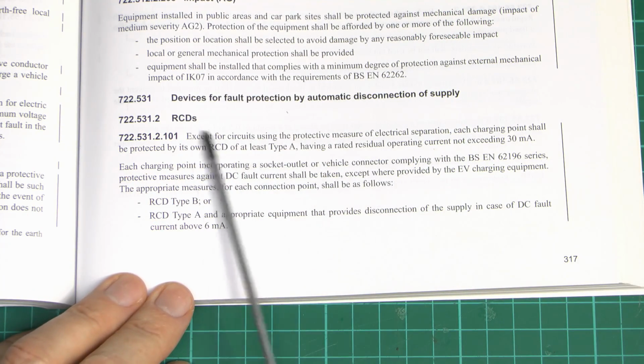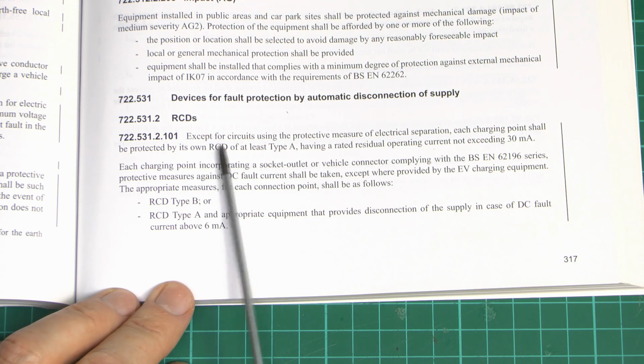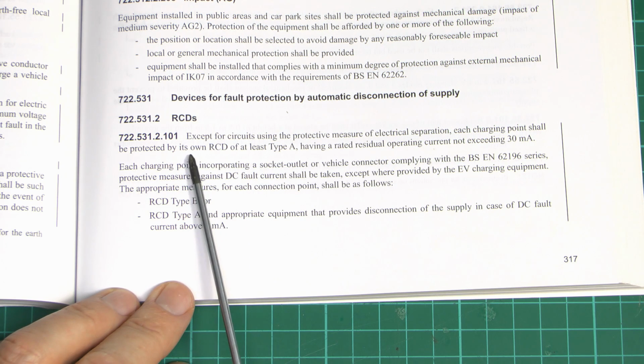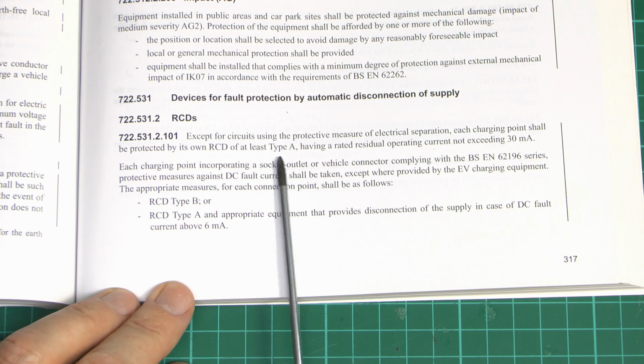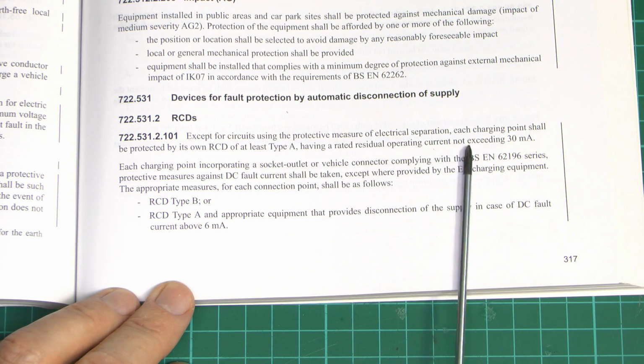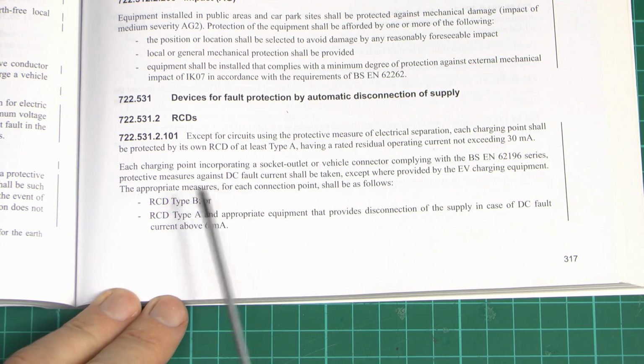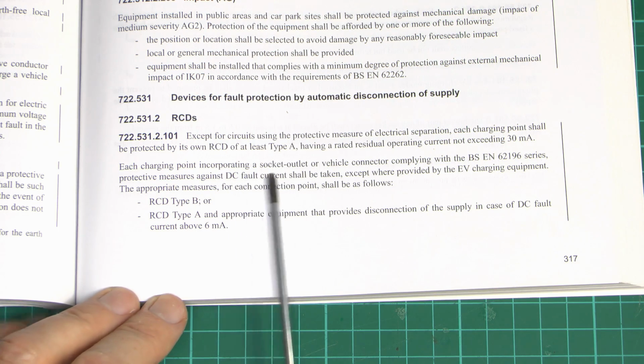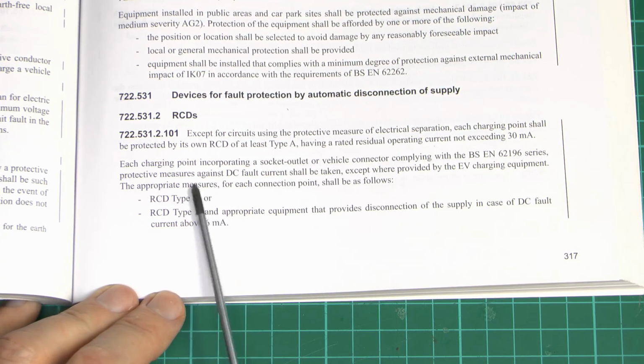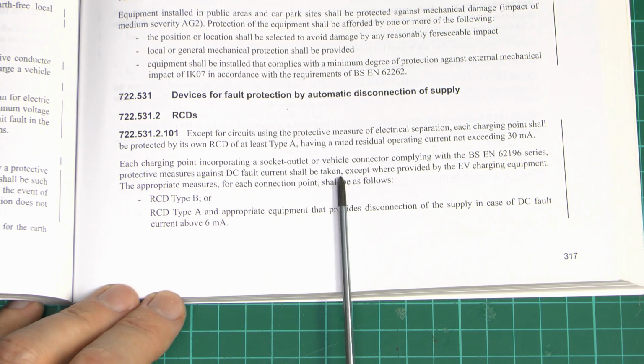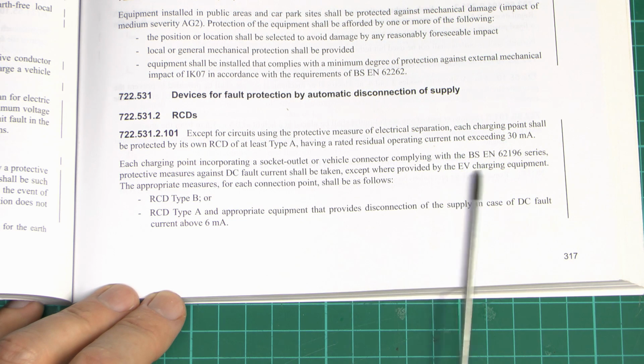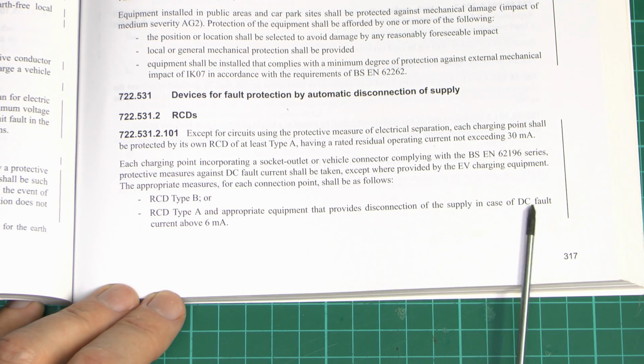Now all of these require an RCD, and the particular type of RCD we require is at least type A, with an operating current not exceeding 30 milliamps, and for each one containing a socket outlet or vehicle connector. Protective measures against DC fault current shall be taken, except where provided by the EV charging equipment, and this can either be an RCD type B, or an RCD type A and appropriate equipment that provides disconnection of the supply in the case of DC fault current above 6 milliamps.